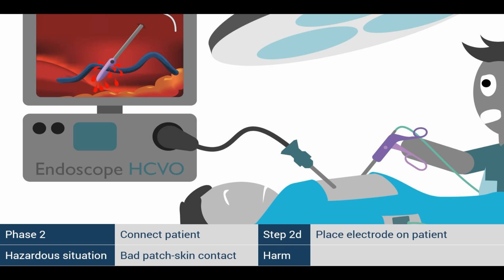And if there is no proper contact at all, the electrical current loop will not be closed and no current will flow when the surgeon presses the foot switch. If the surgeon doesn't notice, the same harms may occur as when the handheld device connector fails.